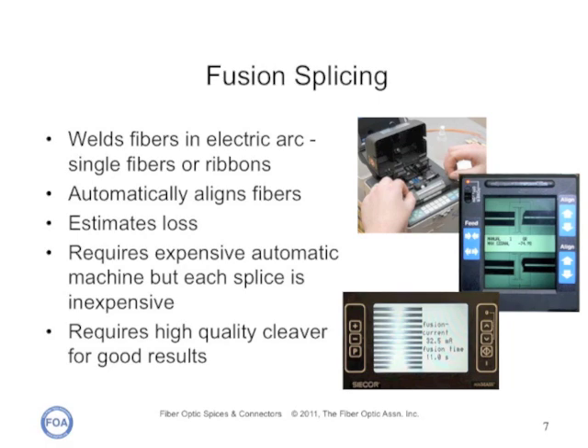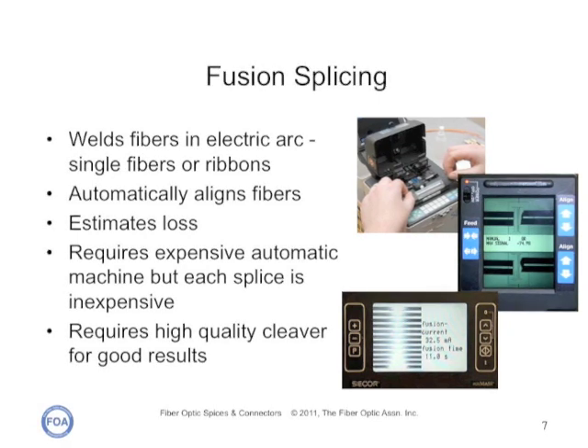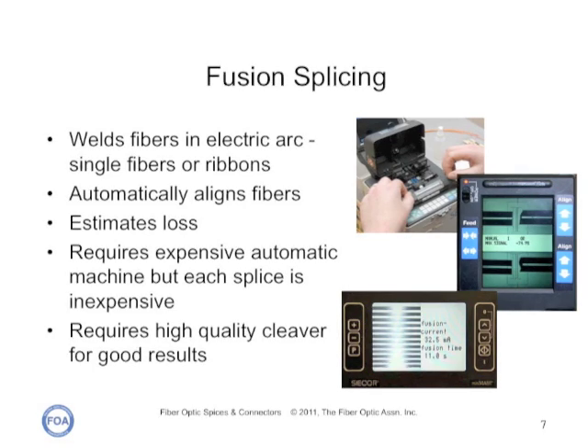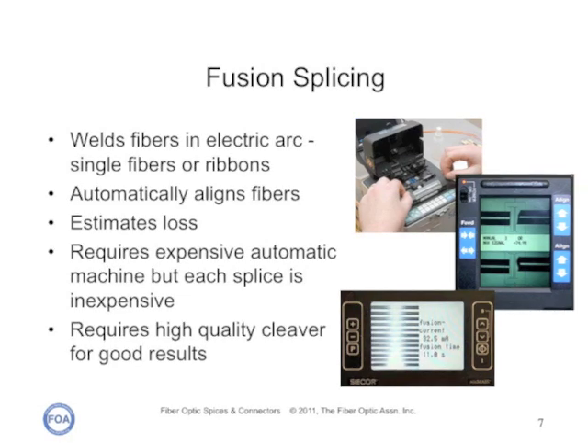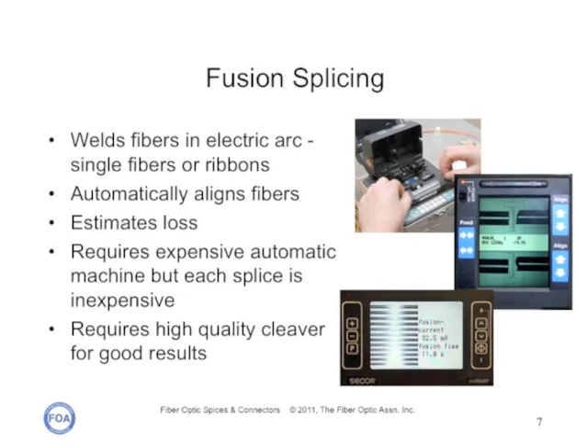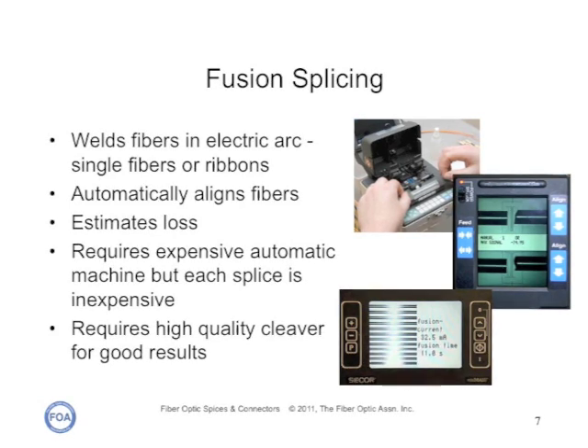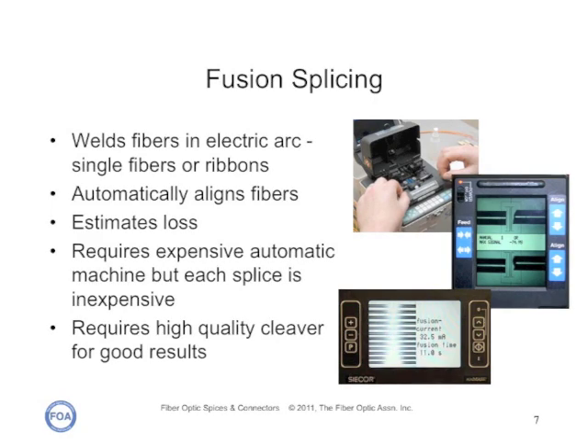Fusion splices are done with an automatic machine that welds the fiber in an electric arc. It can automatically align the fibers and even estimate the loss once the splice is made. The machines can be expensive, but each splice is inexpensive. Each splicer, however, requires a high-quality cleaver, often quite expensive, for best results.